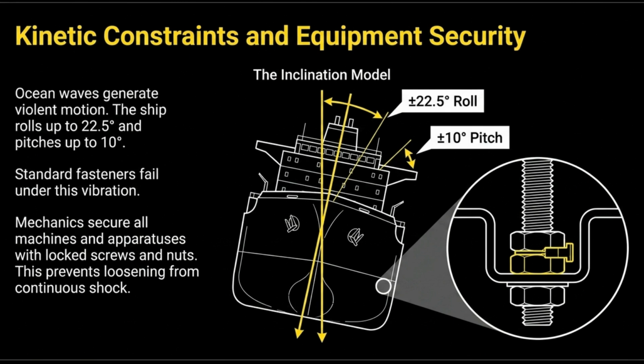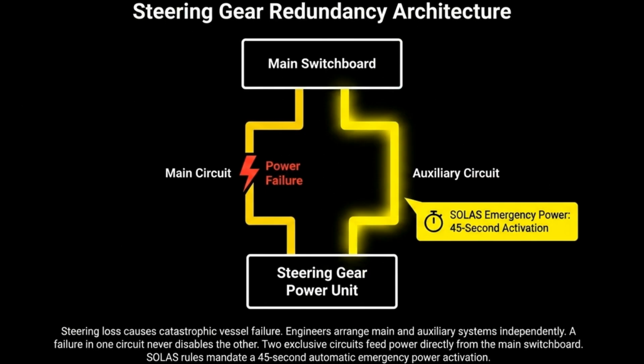Ocean motion creates significant pitch and roll, which can loosen standard fasteners. To prevent this, mechanics use specialized locking screws and nuts to secure all machinery against continuous shock. Redundancy is critical to prevent catastrophic steering failure. SOLAS regulations mandate independent main and auxiliary circuits with automatic emergency power activation within 45 seconds.